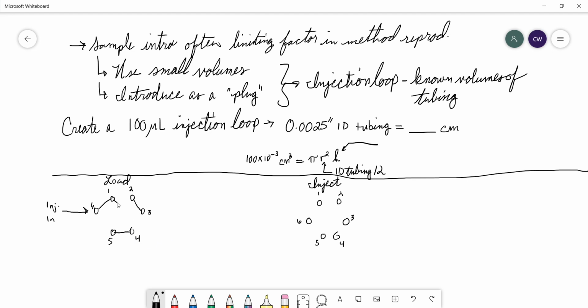If we put our injection column or our injection loop over ports 1 and 4, then when we inject in, we'll have excess go to waste out of port 5. Okay. But what about ports 2 and 3? Well, port 2 and 3 would be our column flows. Okay. So when we're in the load state, we bypass the injection loop on the pump flow. Okay. And we pump directly to the column.